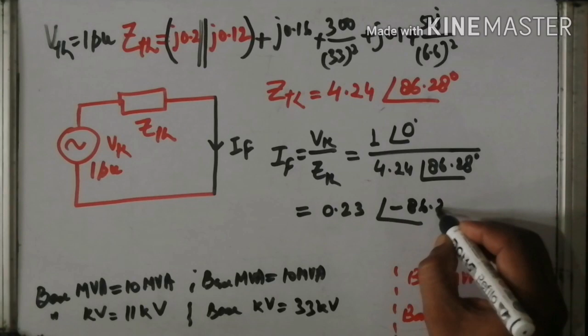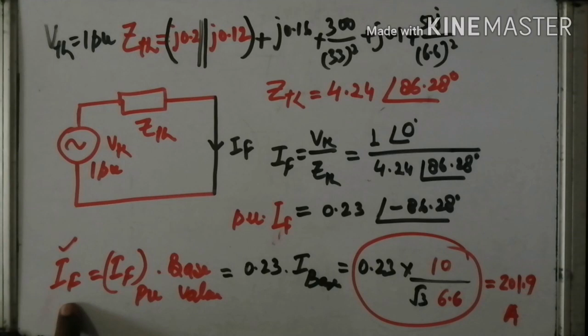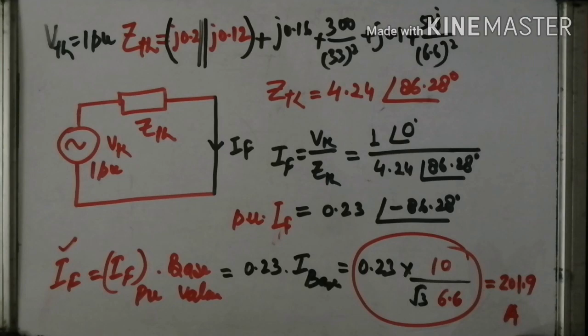But listen to me very carefully. This is the value of current, but in per unit. So for the calculation of actual current, actual fault current, it is necessary to multiply faulty current per unit with the base value. Okay, faulty current is 0.23 into I base, and I base is given by S base divided by under root 3 into V base, right? The value of S base, it is 10, and V base, it is 6.6. After the calculation, fault current, actual value of fault current is 201.9 ampere. Actual value of fault current in the given circuit is 201.9 ampere.